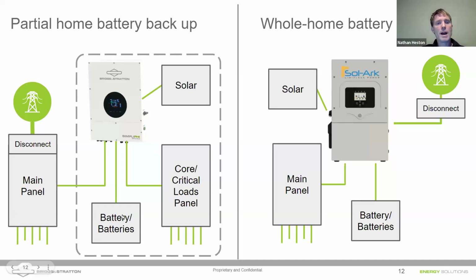They use those batteries then to supply a subset of the loads, only the core critical loads, maybe your lighting, your communication equipment, potentially other things like heating or cooking, if you have enough battery power to do that. You can also, when the grid is down, replenish your batteries from solar. And this is an example of a DC coupled system. You can bring solar in either through AC or DC on both of these inverters.